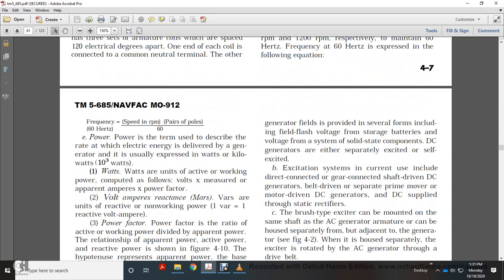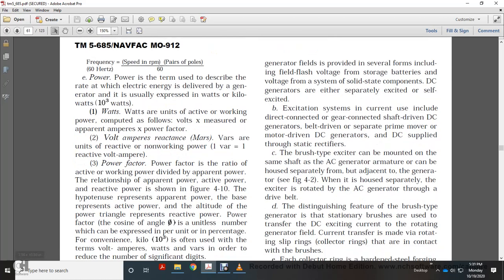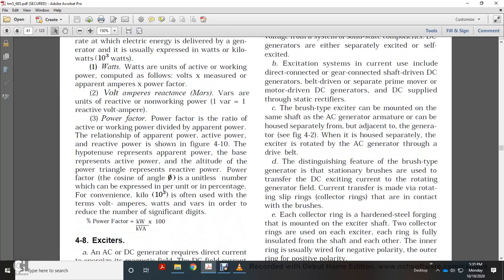Power is the term that describes the rate of electrical energy delivered by the generator, which is usually expressed in watts or kilowatts. Watts are the units of active work, computed with volts measured times amperes measured, times power factor. Volt-amperes reactive, or vars, is the unit for the reactive, non-working power. One var is the reactive volt-ampere power factor.